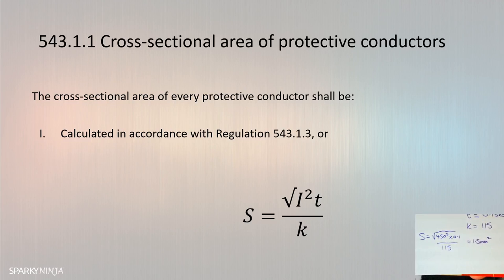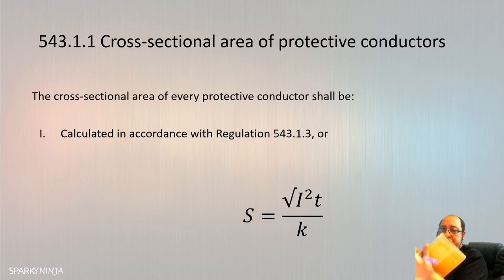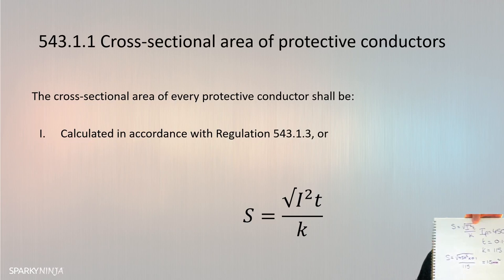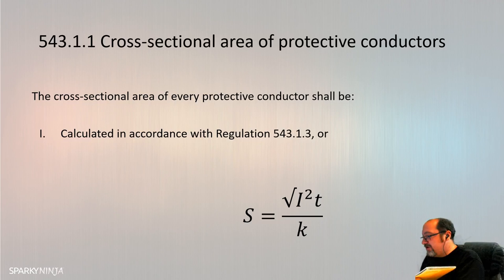All right. So obviously the protective conductor coming with that 10 mil, it's going to be fine. Let's adjust it slightly. Let's pretend the protective device is slightly different. Let's change that protective device to the BS3036. Okay. So, because, yeah, why not? All right. With an MCB, you can see why a lot of circuits kind of get away with design with an MCB, because it works. The device's speedy characteristics and everything just works very well.